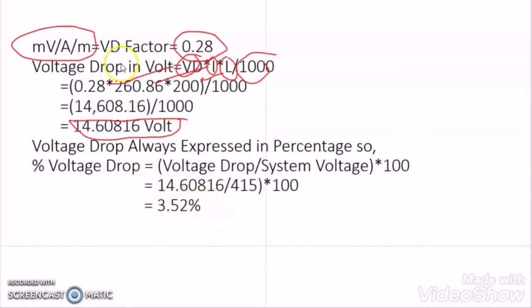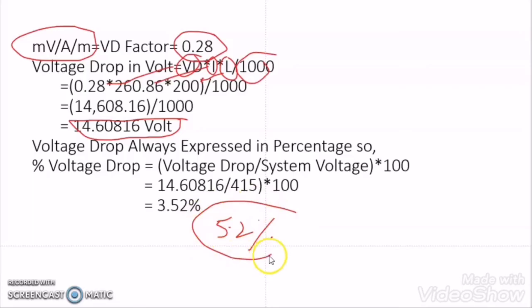Suppose after our calculation we find that the voltage drop percentage is coming to 5.2%. In that case we have to go for a higher cable size. The higher size above 185 mm² is 240 mm². Or, we have to go for 2 runs of a smaller cable, maybe 95 or 120 mm² — 2 runs of that cable — which will be another case.